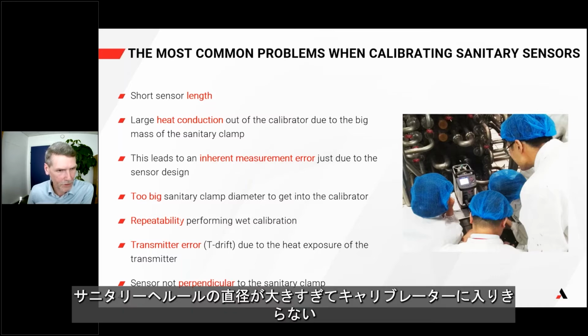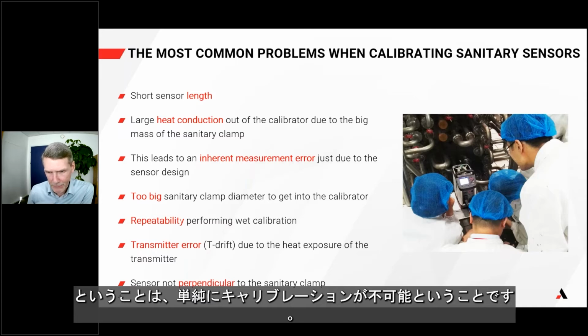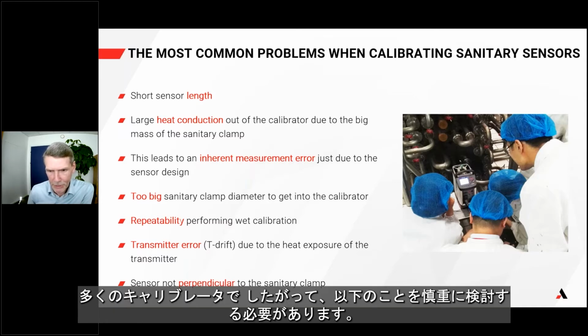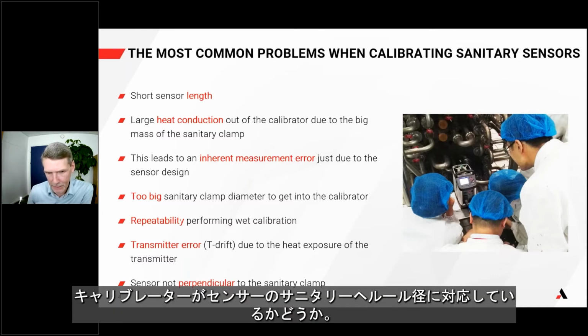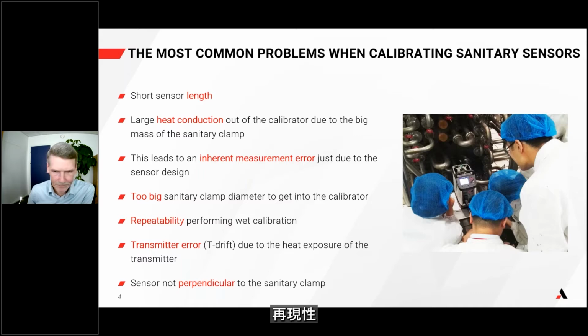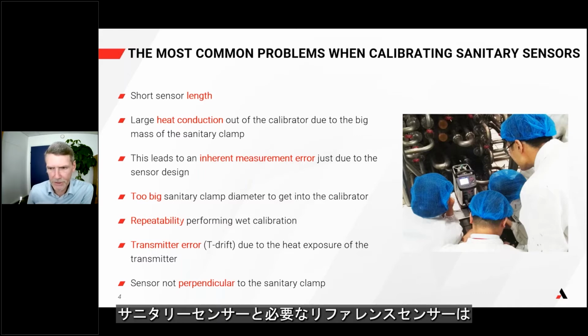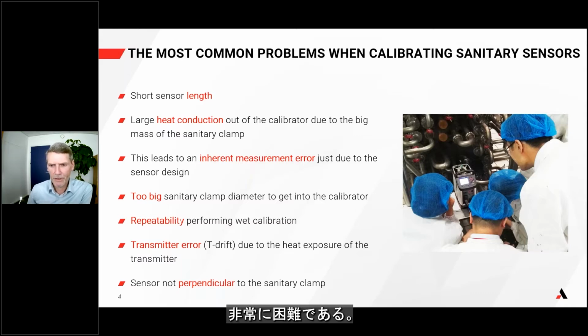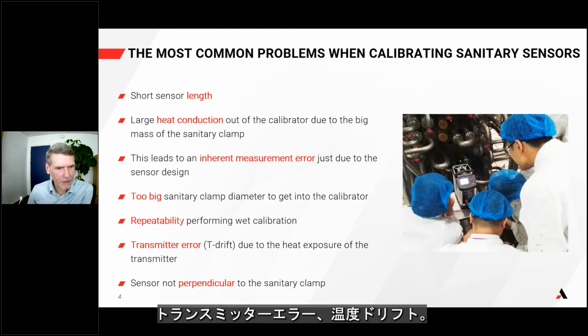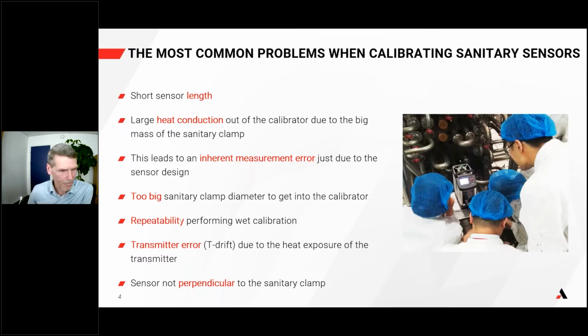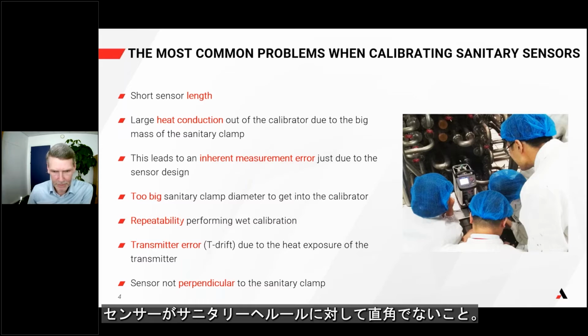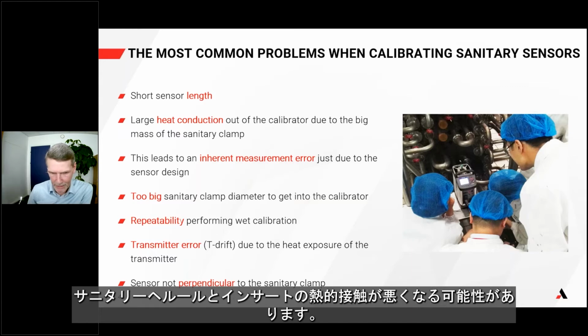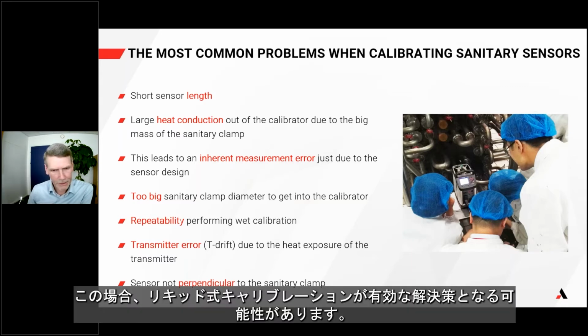Too big sanitary clamp diameter to get into the calibrator. And that simply means that the calibration is impossible in many calibrators. You therefore have to carefully examine if the calibrator can accommodate the sanitary clamp diameter of your sensor. Repeatability. Due to the fact that it is very difficult to place the sanitary sensor as well as the needed reference sensor in the same position for successive calibrations. Transmitter error, temperature drift, due to the heat exposure of the transmitter, meaning that the transmitter will also influence the results. Sensor not perpendicular to the sanitary clamp. This can cause bad thermal contact between the sanitary clamp and the insert. Using wet calibration could be a good solution here.